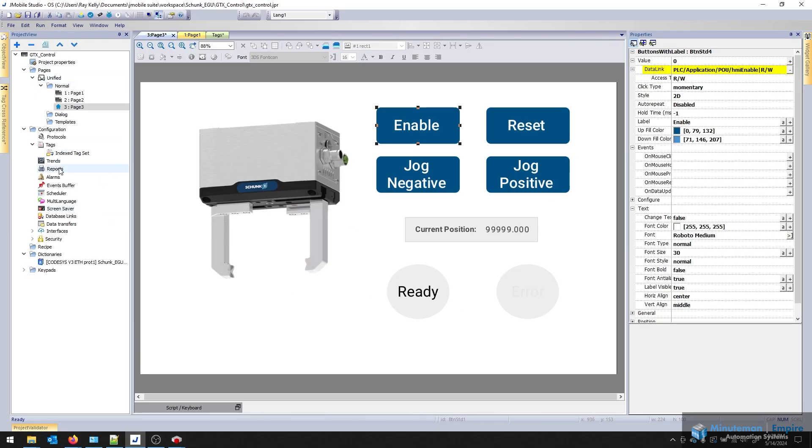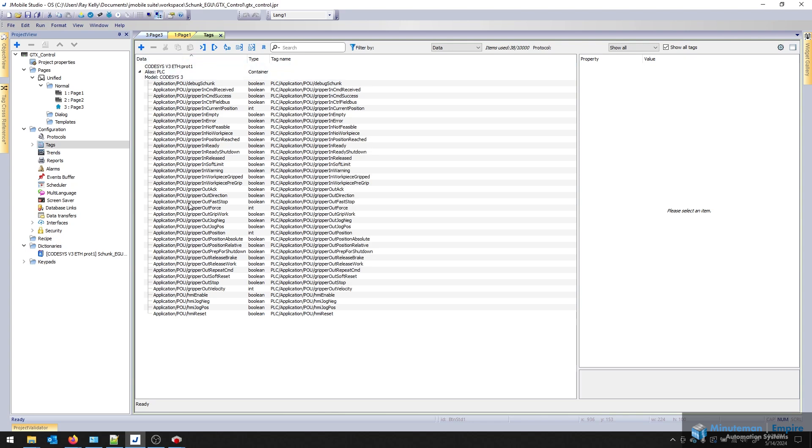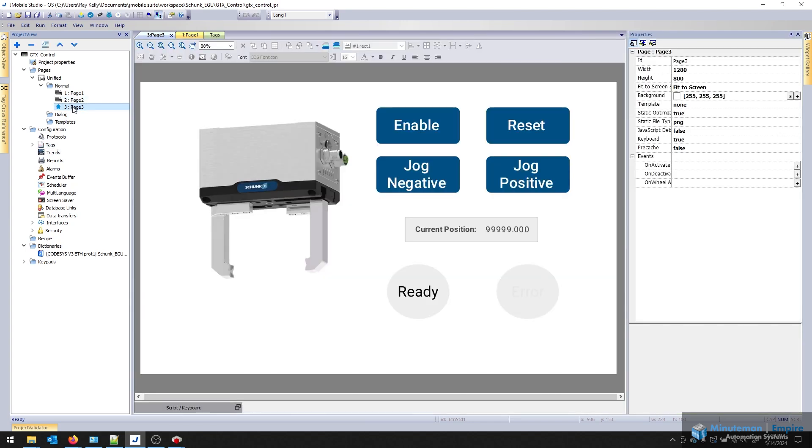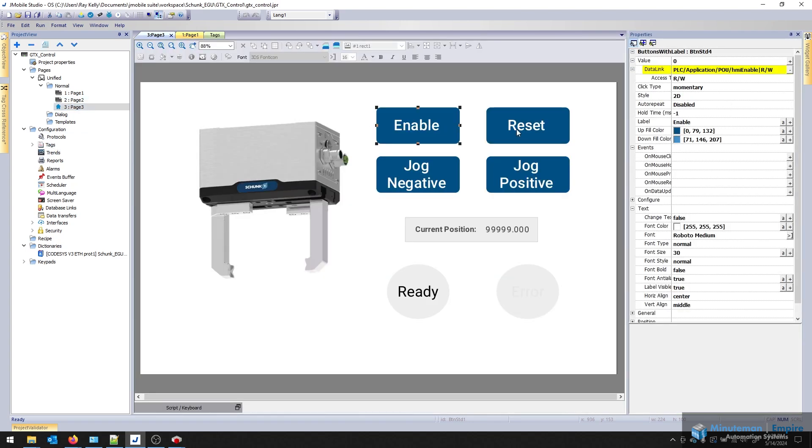Coming over here to my symbol configuration, if you're using the XR specifically, you'll need to add this file so that you can export your tags into J-Mobile. And in J-Mobile, you can go in here to import those tags, and it'll appear here. Once you go to your page, you can then add various buttons, status, symbols, and control signals, and then tie them to the tags in your PLC. Making very easy, quick integration package.